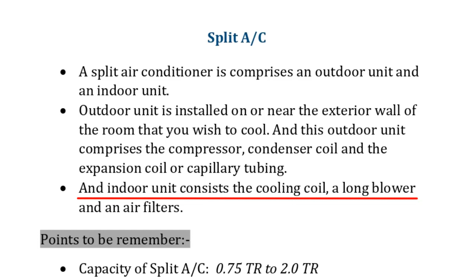For this unit we don't have to provide any slot in the wall as with a window AC, but simply we have to make a small hole, approximately 5 to 8 centimeters, so you can easily pass your drain pipe, refrigerant pipe and electrical cable. The available capacity of split AC is from 0.75 TR to 2 TR. Split AC is also available in 2.5 TR capacity, but it is not recommended to install.